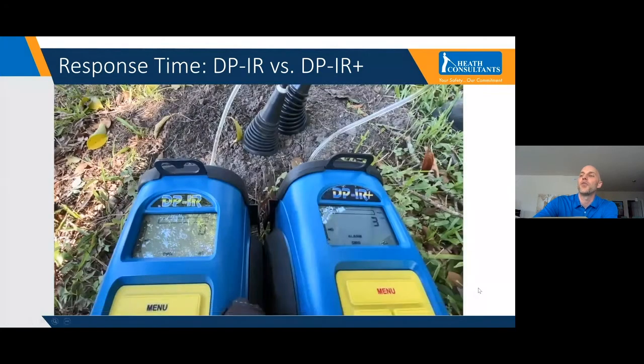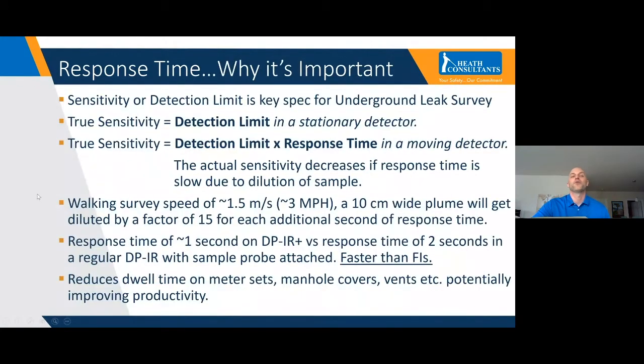Okay, so what I was talking about there is response time. That's the big improvement on the DPIR Plus: the upgraded optics, board, and pump really play a big part in the increased response time. The old pump was drawing about 1.2 liters a minute, the new pump is 2 liters a minute.